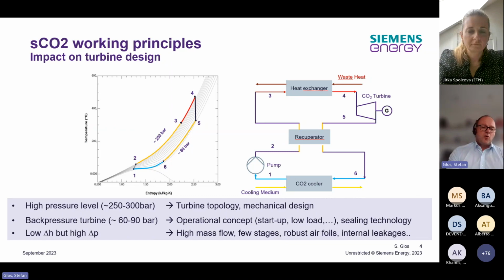Then we have a comparably low expansion line, meaning quite a low enthalpy drop but a significantly high pressure drop. From the low enthalpy drop you can conclude that you need a high mass flow circulating in the system. On the other hand, you will get quite few stages, at least significantly fewer than in a steam turbine, but these stages have to deal with that large pressure drop. That leads to robust airfoils, and furthermore, the internal leakages become more important, and you have to take care of that as well.